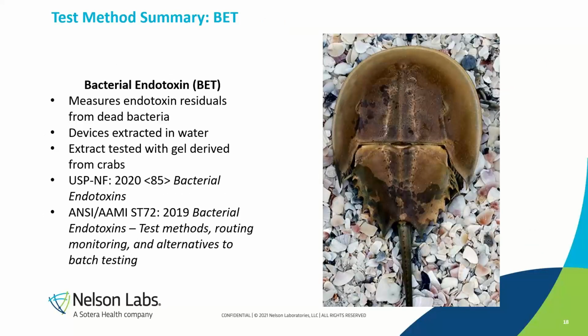Next up is bacterial endotoxins. We measure this using a turbidimetric method, extracted in water, for USP 85 and AAMI ST72. This does have industry acceptance criteria. Side note, endotoxins are often introduced through water sources. So the cleaning step itself might be introducing endotoxins to your device, which are very difficult to remove. It does not equate to sterilization. They're two separate ideas that often get confused.